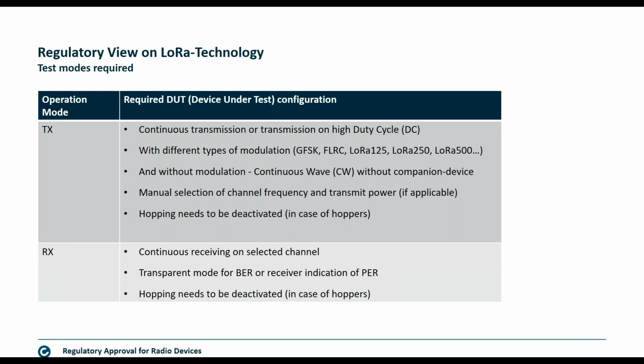1,440 steps with continuous wave emission takes 20 minutes. But if the device only sends one signal every 10 minutes, that's 10 minutes times 1,440 positions - no one wants to pay for that. So we definitely recommend making up your mind before coming in for testing. We can advise what we need from you for the most efficient, price-sensitive testing.